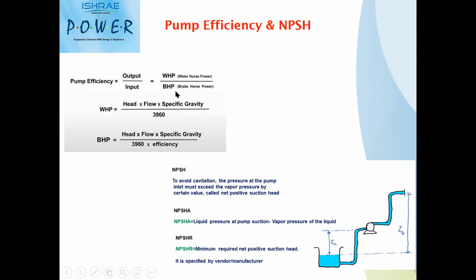And then what is the input? Input, whatever we are giving, is the brake horsepower, like what is the power required for the pump to perform that flow and head. So in this case, the shaft power available is the power required for generating flow and head, and we get the hydraulic efficiency of the pump. So particularly when we are calculating input power to the motor, or if the pump is driven by VFD, input power to the VFDs, that is called the overall efficiency of the pump.